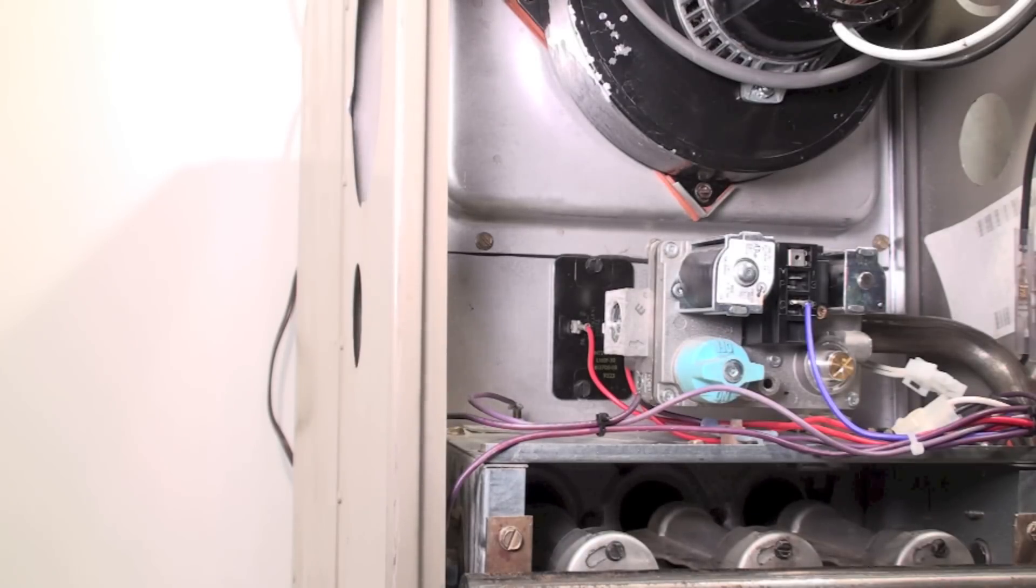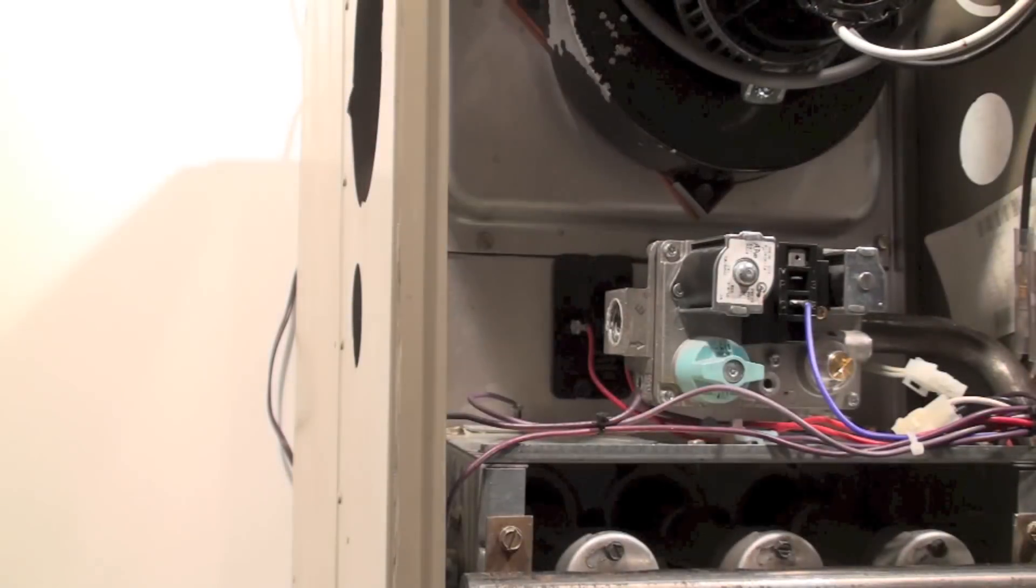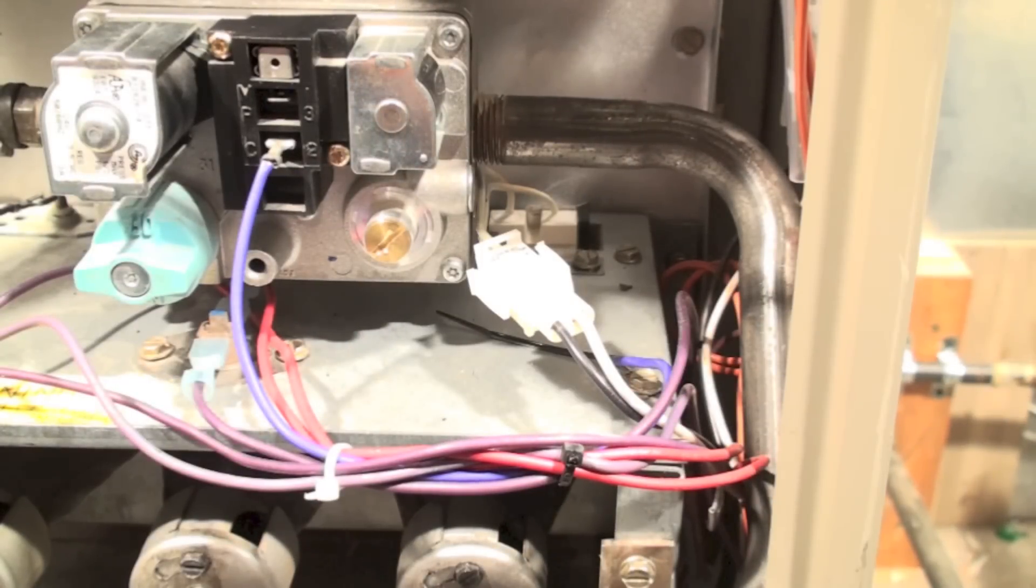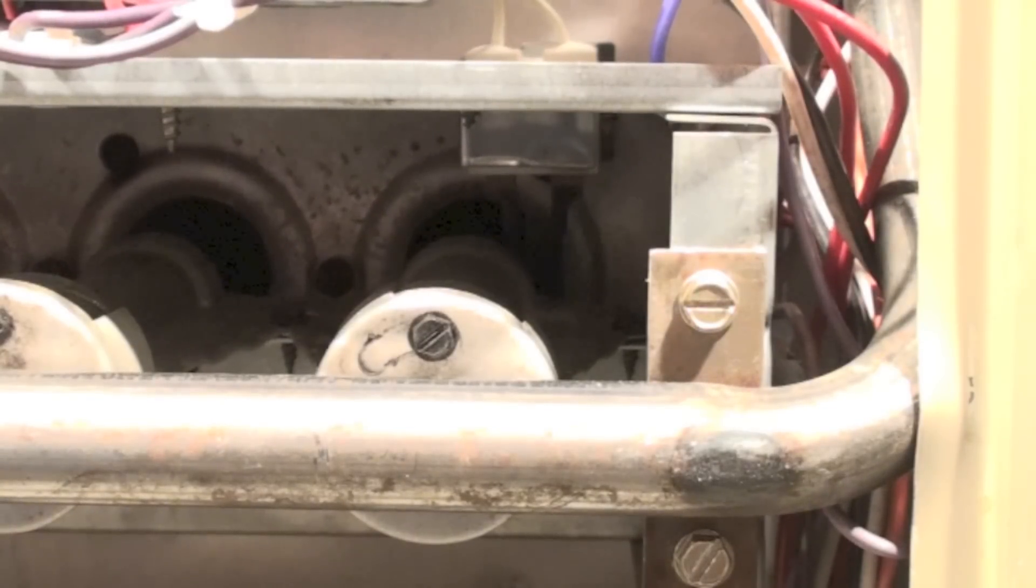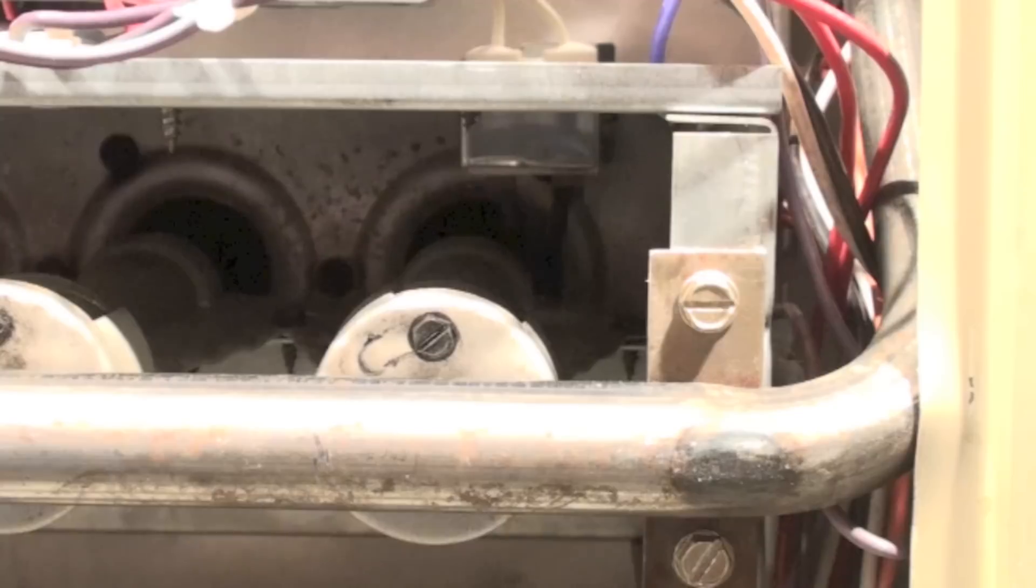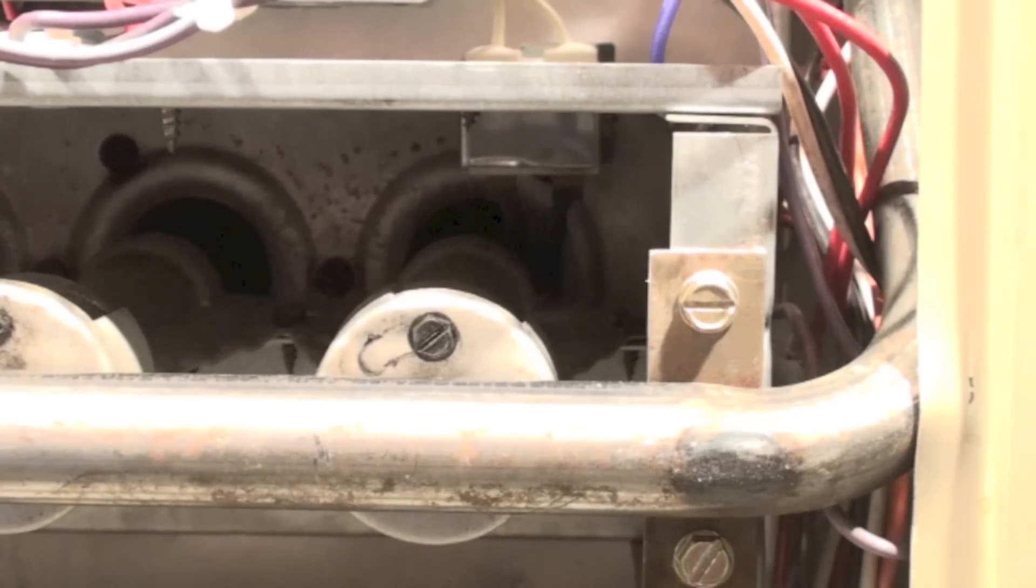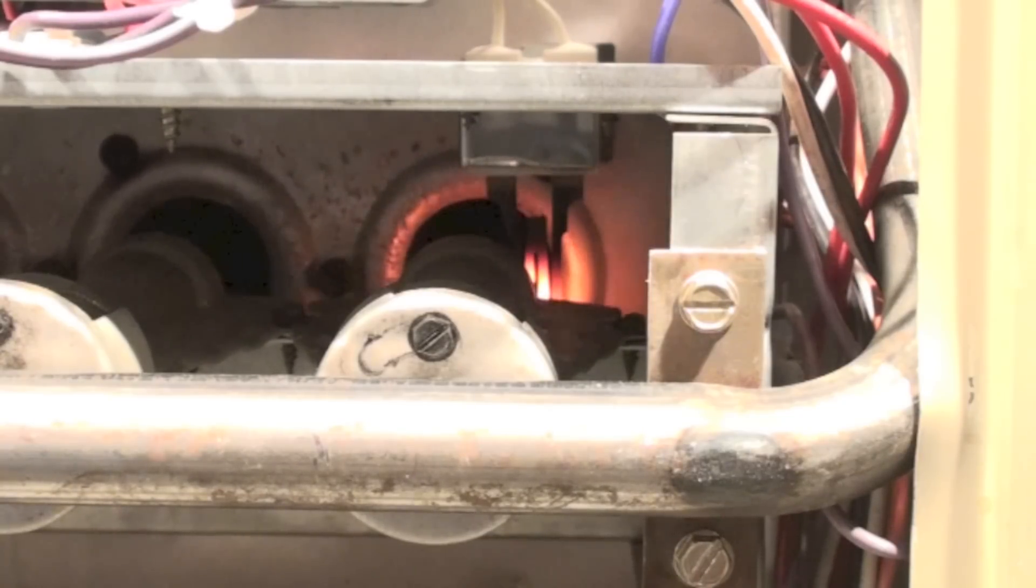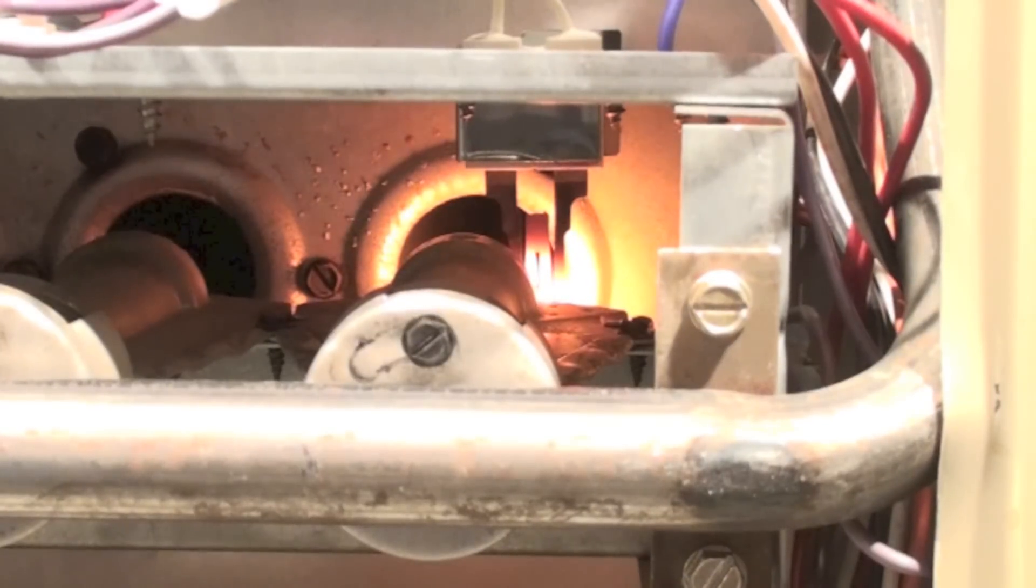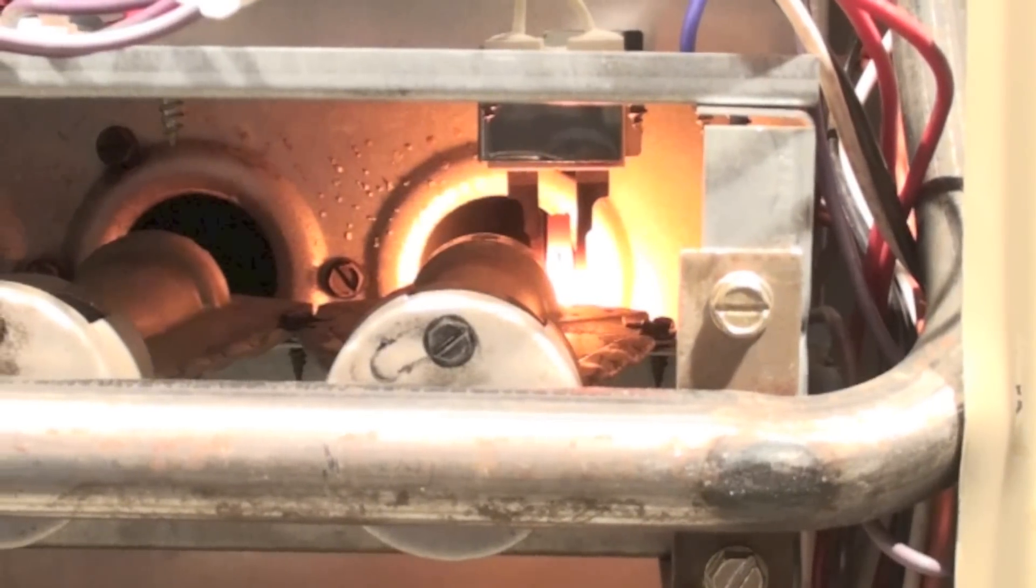The igniter is going to be the hot surface igniter. We're ready for the hot surface igniter to come on. We're going to have a warm-up period of 17 seconds for the hot surface igniter. I heard a click, so it is starting to warm up now. You can see the glow start to come on there.